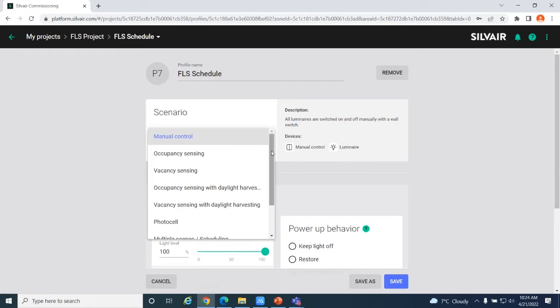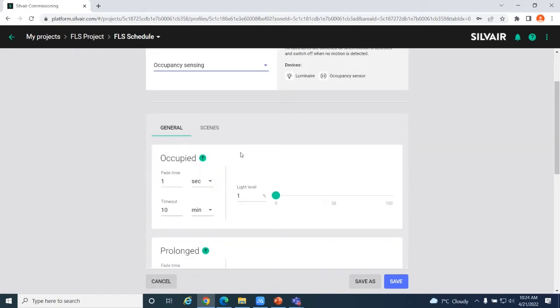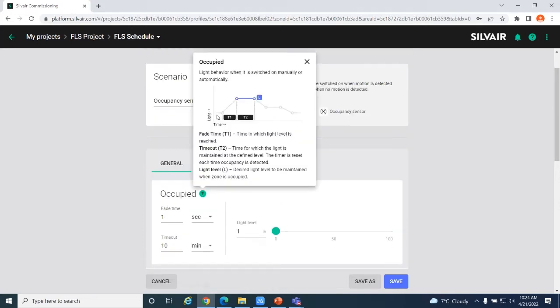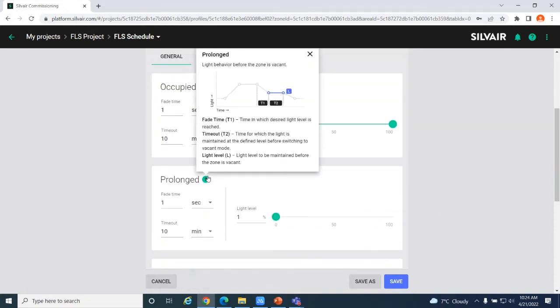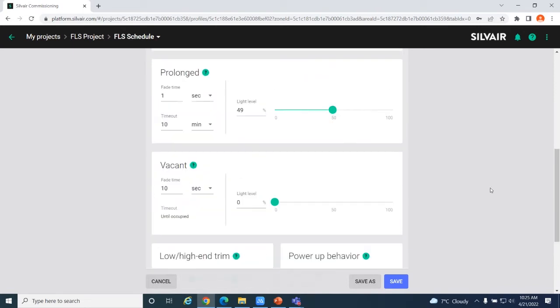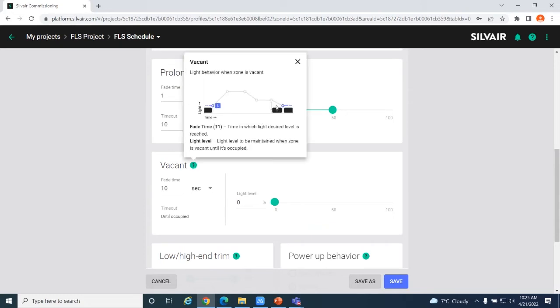If you want occupancy sensing, for example, if you know your zones are going to have occupancy sensors, this is what you need to define. When you detect occupancy, you want the lights to turn on, and on the fade time here I put in a second, then I want to stay there for 10 minutes at 100%. After that initial period has elapsed, I'm going to go down to an intermediate level, and stay there for another 10 minutes. Then the final stage is when it's vacant, where basically you want to be at 0 in most cases.